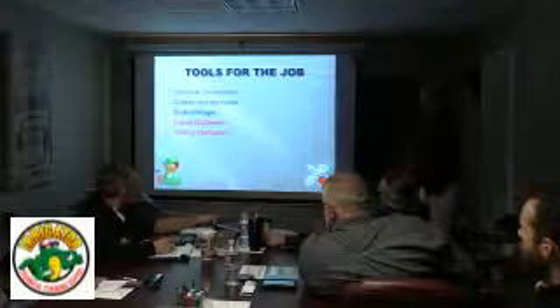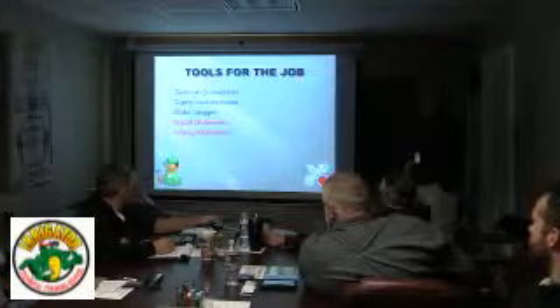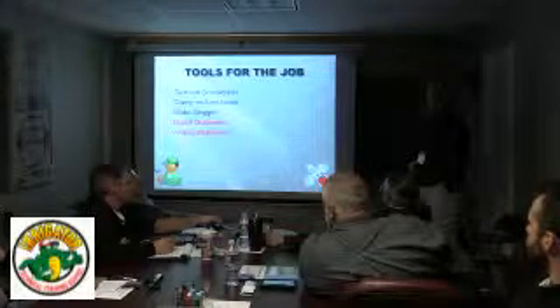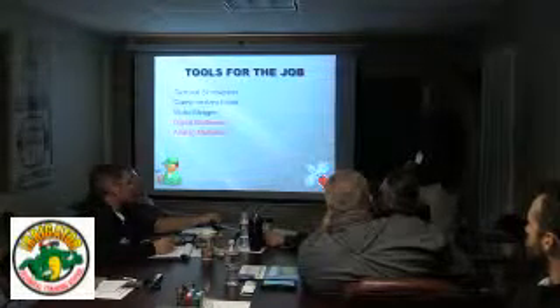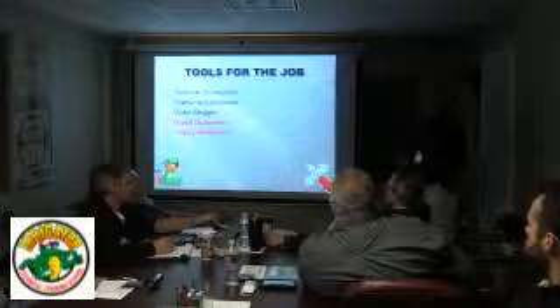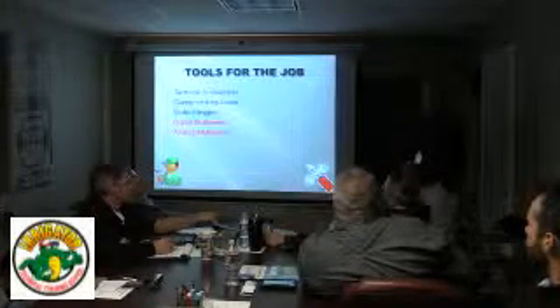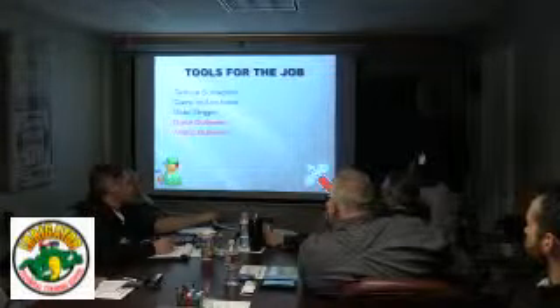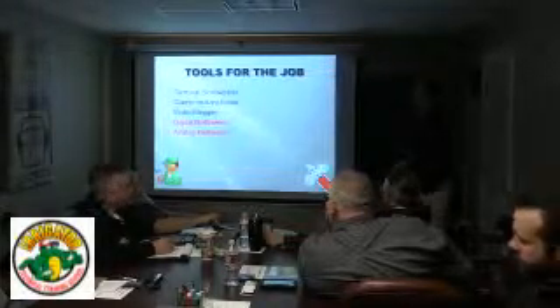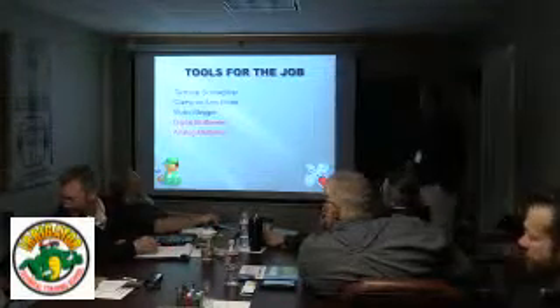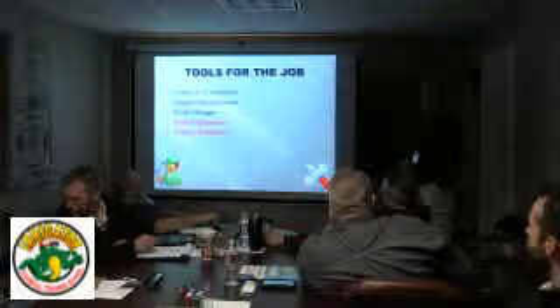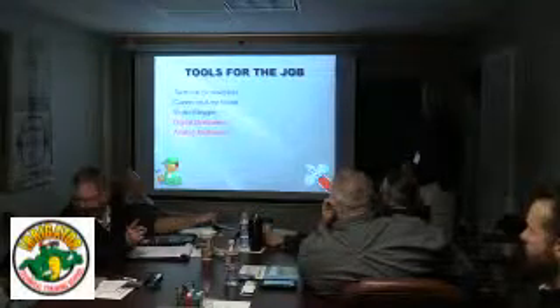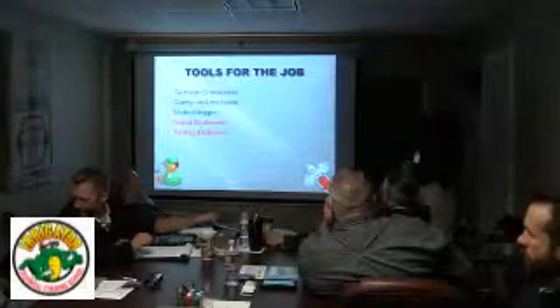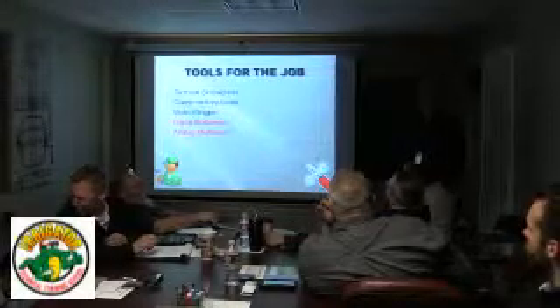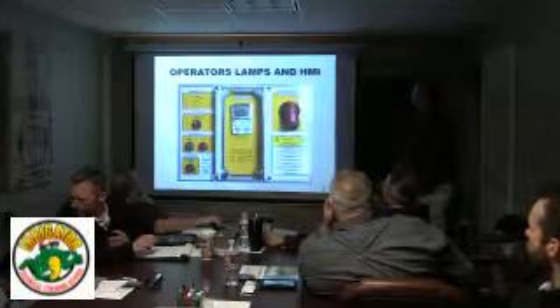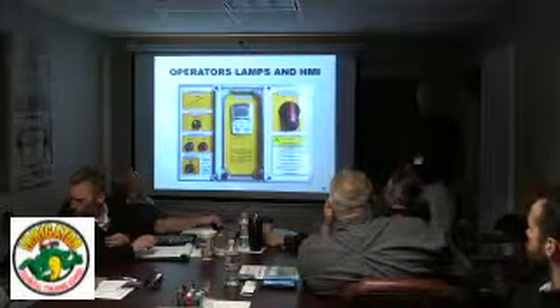And then of course the digital multimeter. They used to recommend an analog multimeter, the drive manufacturers did, but we found that most of the newer digital multimeters now will measure the output of a drive okay well enough to do your basic troubleshooting. So an analog multimeter, I don't think there's many around anymore. We don't use them much anymore either, but a good digital multimeter is almost a must if you're troubleshooting on a pump station or calling for technical support, something. We're always having to check, measure something. True RMS. Right.